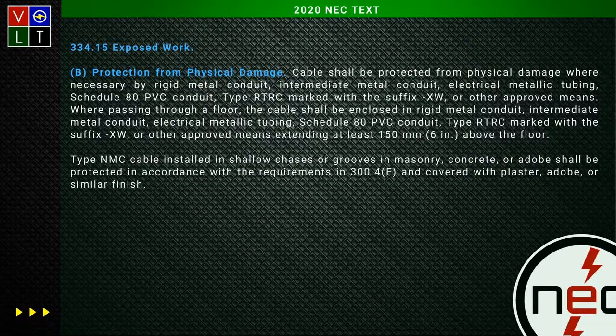If you look, this does the final tie-in, because 334.15B talks about protection from physical damage. So Article 300 gives the general rules, and this covers the wiring methods themselves. It says it can be protected from physical damage where necessary using RMC, intermediate, EMT, Schedule 80. It goes through and tells you these can be used to provide this type of protection.